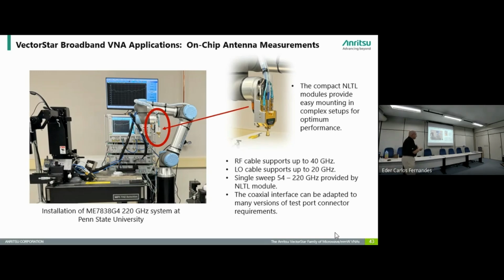It's whatever I attach from the interface where I do the calibration to where I connect to the device. That's the most sensitive cable. And I've eliminated the one that goes up to 54 gigahertz from here, so we're not using it. That would have been a sensitive one. That connection would have been sensitive to this kind of movement, because that's the connection coming directly from the VNA. It goes right through the module and ends up bringing the signal from 70 kilohertz to 54 gigahertz.